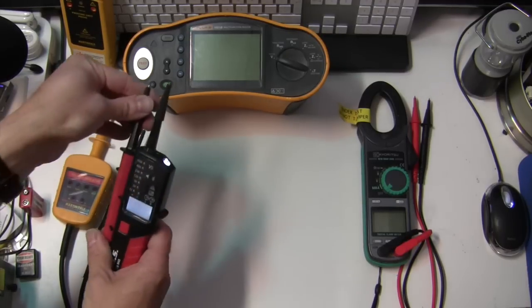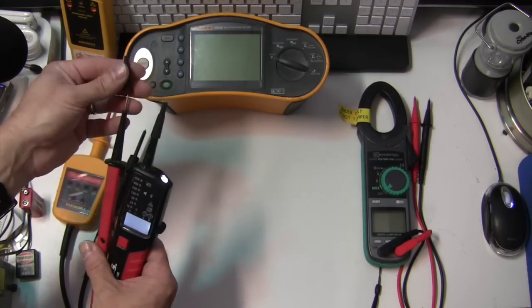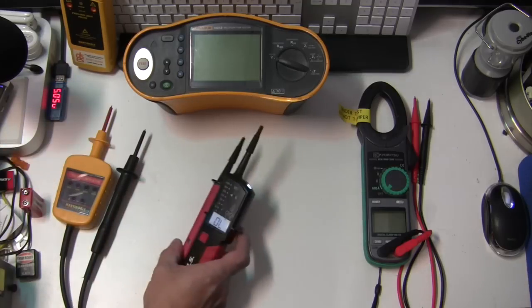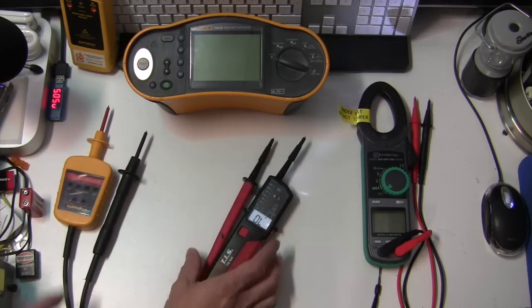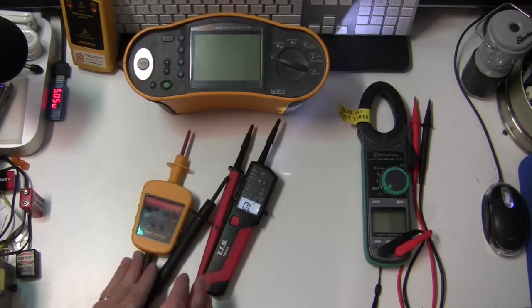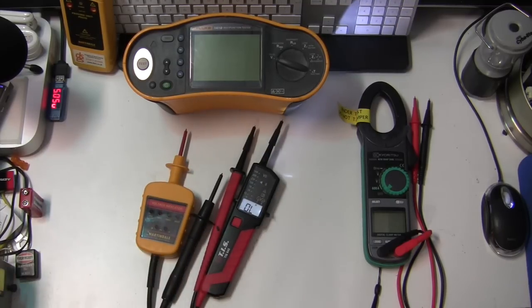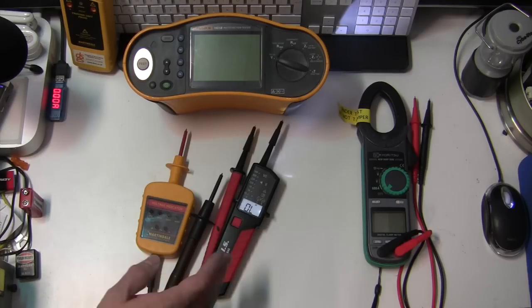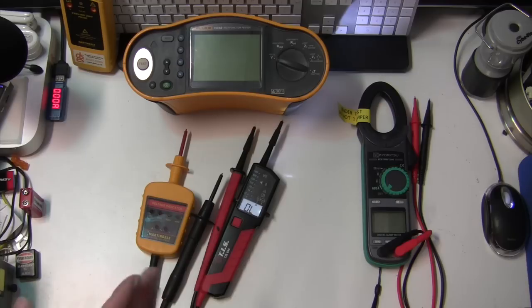The GS38 tip covers can be removed on this for some extra reach should you need to get into tight places. Neither of these indicators have an on-off switch, so they'll react immediately whenever voltage is applied to their probe ends. For safety on the TIS model, if the batteries are flat or missing, it will still give an audible and visual warning of the presence of voltage, albeit not a measured indication.